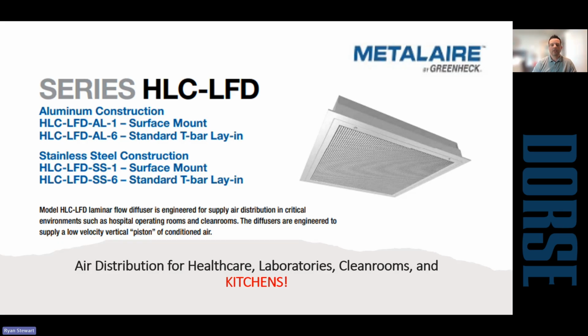We don't want to see any directional diffusers within 10 feet of a hood. We also don't want to see any HVAC returns in proximity to the hood. Ideally, for best performance, you're looking for a 0 velocity at the cooking surface.